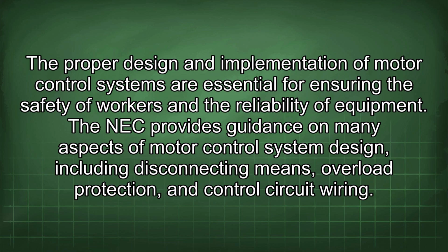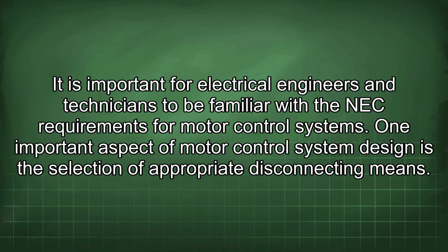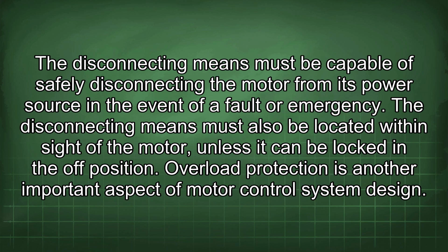The NEC provides guidance on many aspects of motor control system design, including disconnecting means, overload protection, and control circuit wiring. It is important for electrical engineers and technicians to be familiar with the NEC requirements for motor control systems. One important aspect of motor control system design is the selection of appropriate disconnecting means. The disconnecting means must be capable of safely disconnecting the motor from its power source in the event of a fault or emergency. The disconnecting means must also be located within sight of the motor, unless it can be locked in the off position.